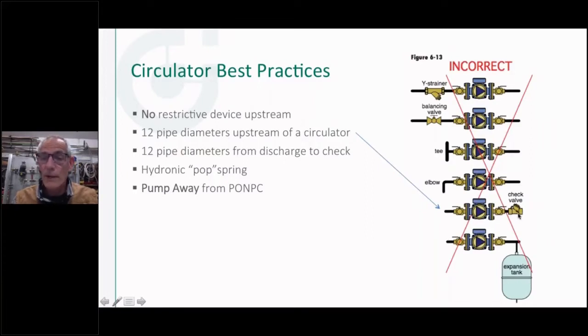And if you do buy a check valve that you're going to put on the discharge like that, you want to get a hydronic specific check valve, not a swing check valve. Get something that's got a spring-loaded check in it and also a conical shape to it, so it's got a nice flow passage and doesn't make noise and vibrate and clatter around in there. So we make a check valve like that. Other people do too. Watts, Conbraco make hydronic specific check valves if you want to put one in the system.